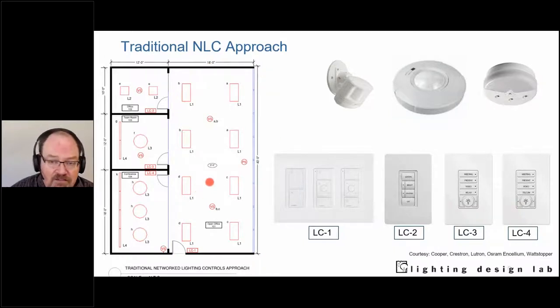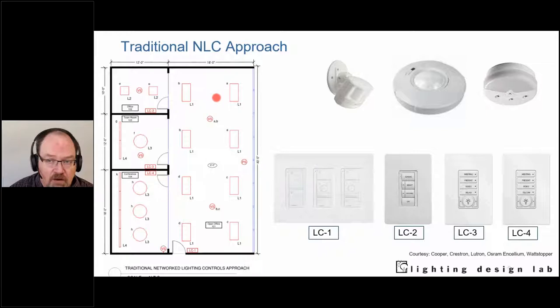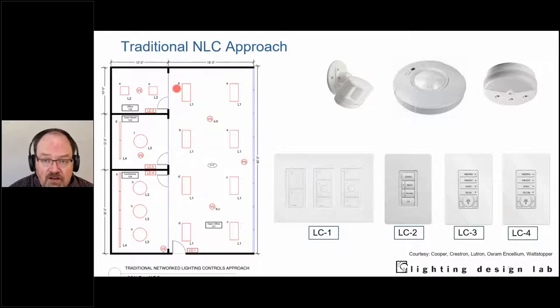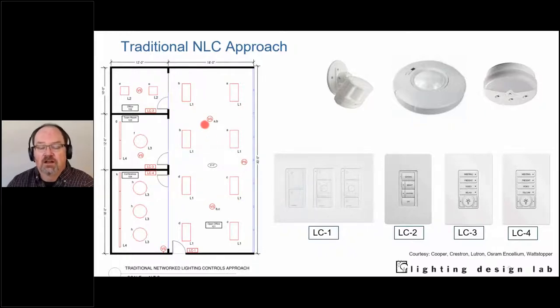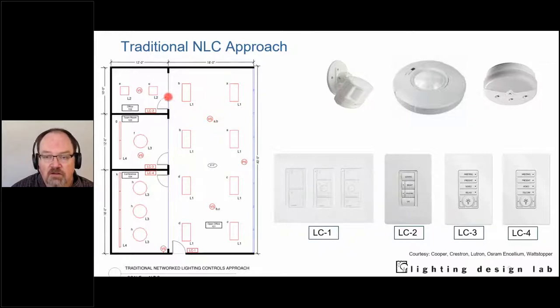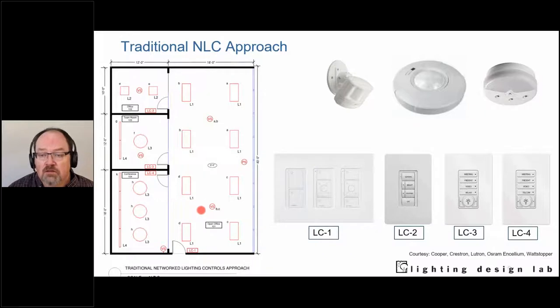For code minimum, I'd have one control zone for the primary daylight zone and one for the secondary. Personally, I like to break things up further — someone working on a Sunday might only need lights in part of the space. So I'd break it into quadrants: one zone for primary daylight, one for secondary, and then subdivide so I can control these areas separately. Vacancy sensor A-B controls one zone pair, vacancy sensor C-D controls another, giving more granular control, potential energy savings, and happier people.